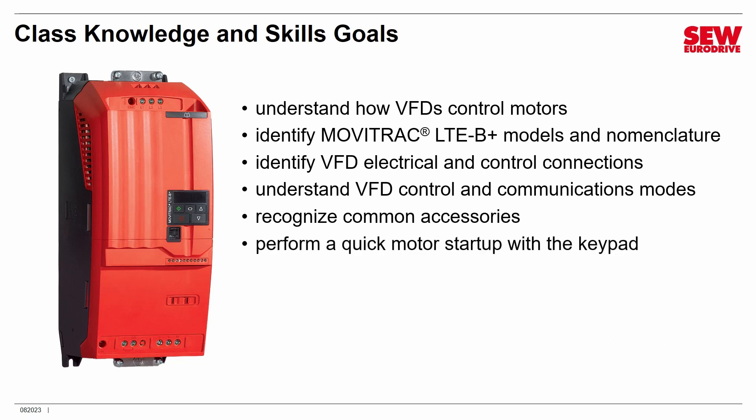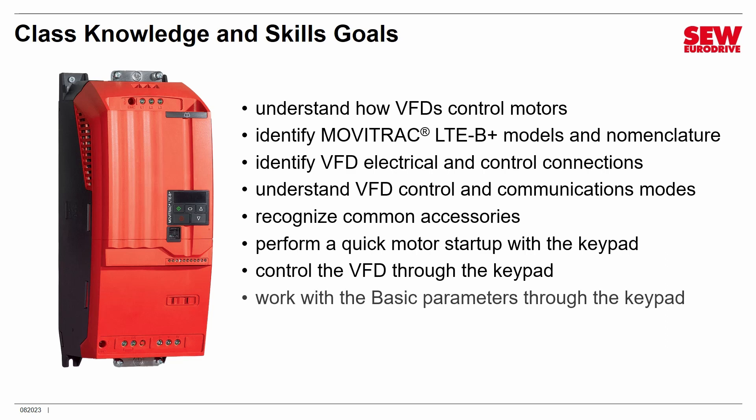Then we'll talk about how to do a quick motor startup using just the built-in keypad — it's a quick and painless task. We'll control the VFD using just the keypad, showing how it's a wonderful choice for simple shaft-spinning applications. We'll work with the 14 basic parameters needed for basic setup. But then we're going to show you that the LTE B-Plus is actually a very powerful VFD. We'll switch to extended parameter mode, where you'll have access to 116 parameters to customize the MOVITRAC LTE-B+ for more sophisticated applications. Although this is an entry-level VFD, it is by no means low in capabilities.